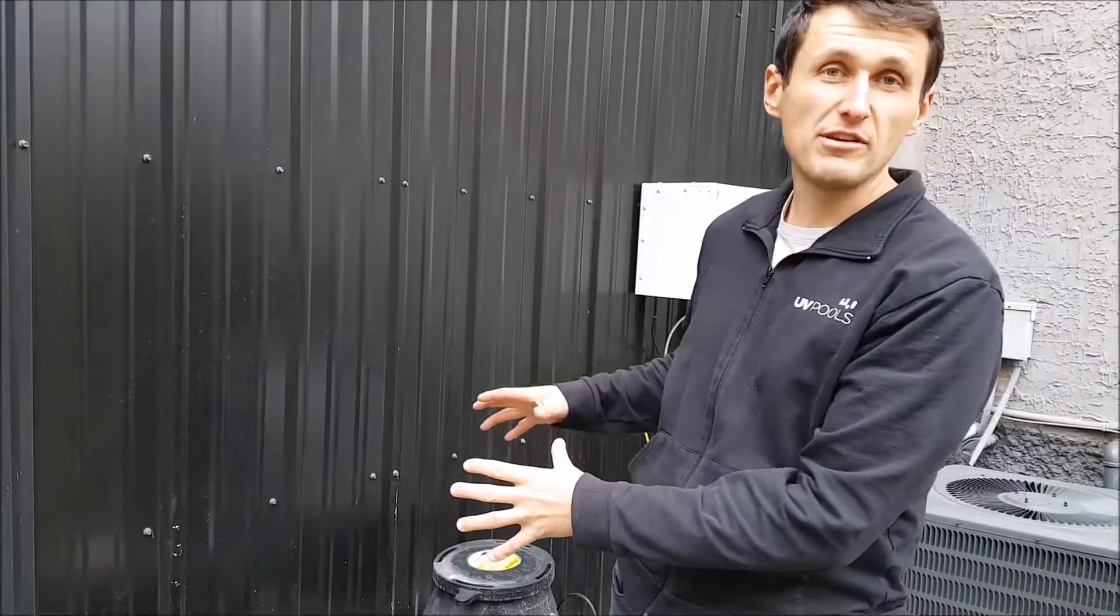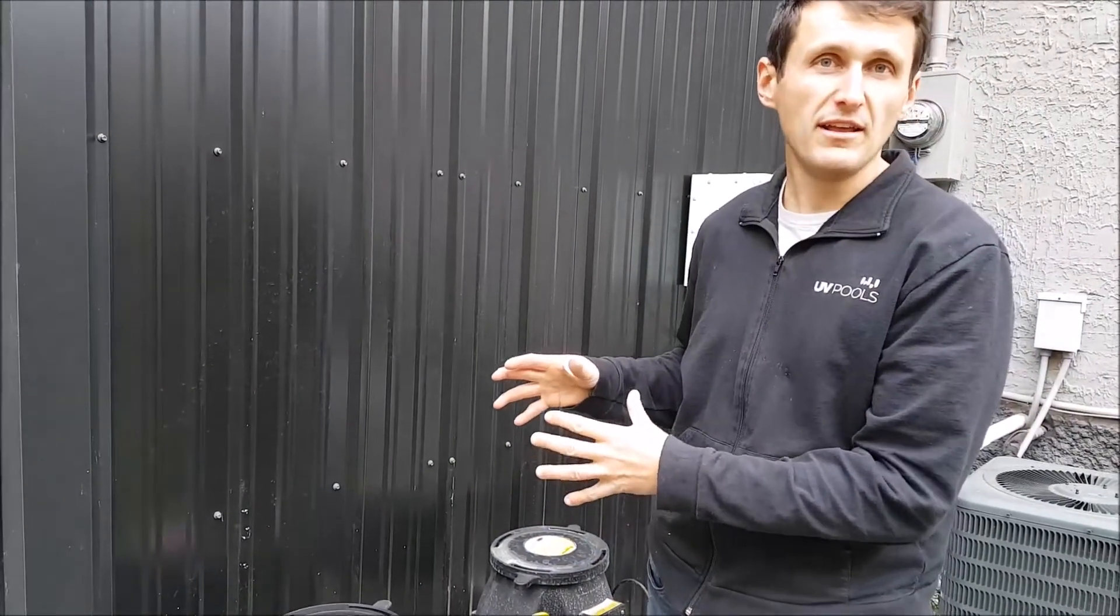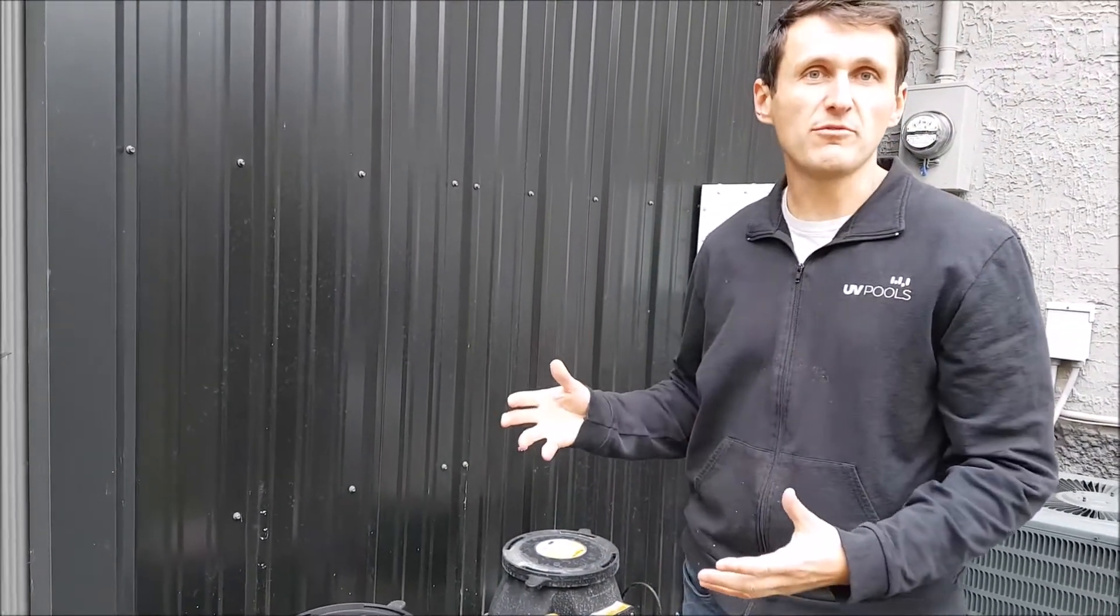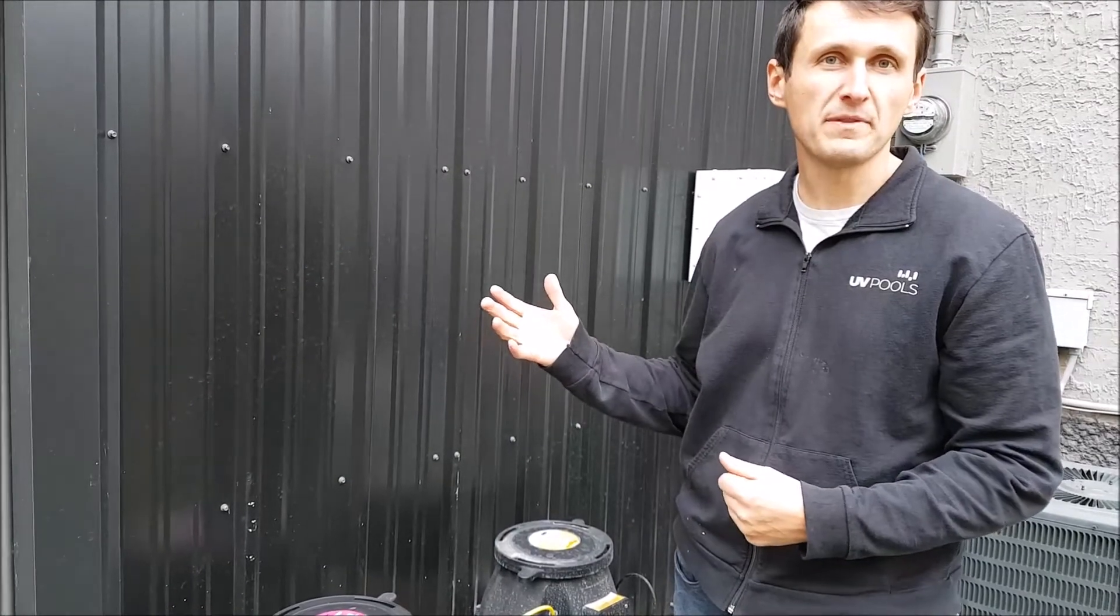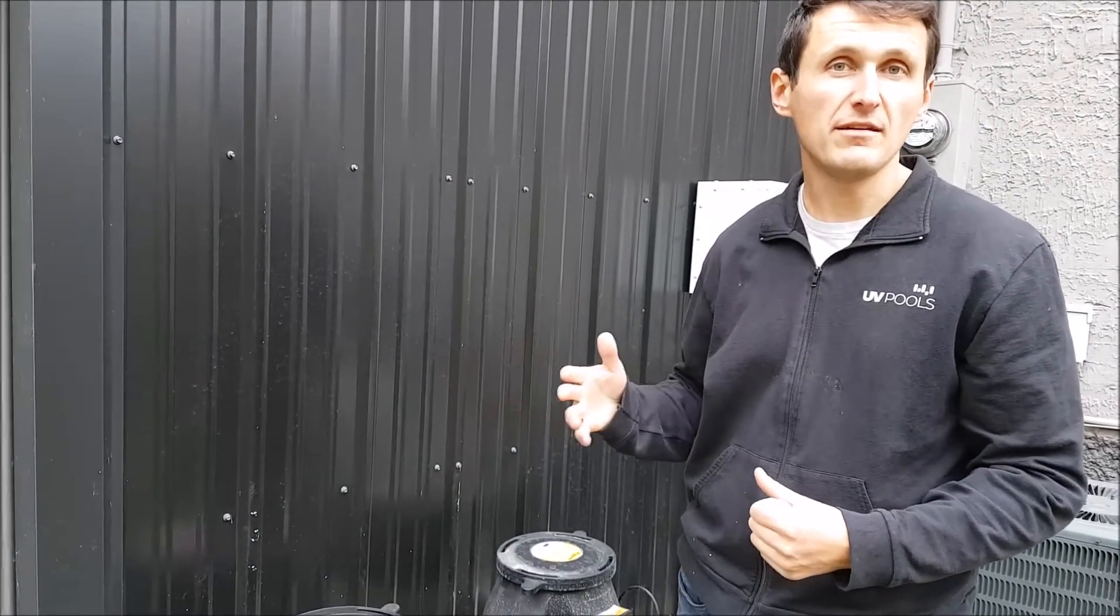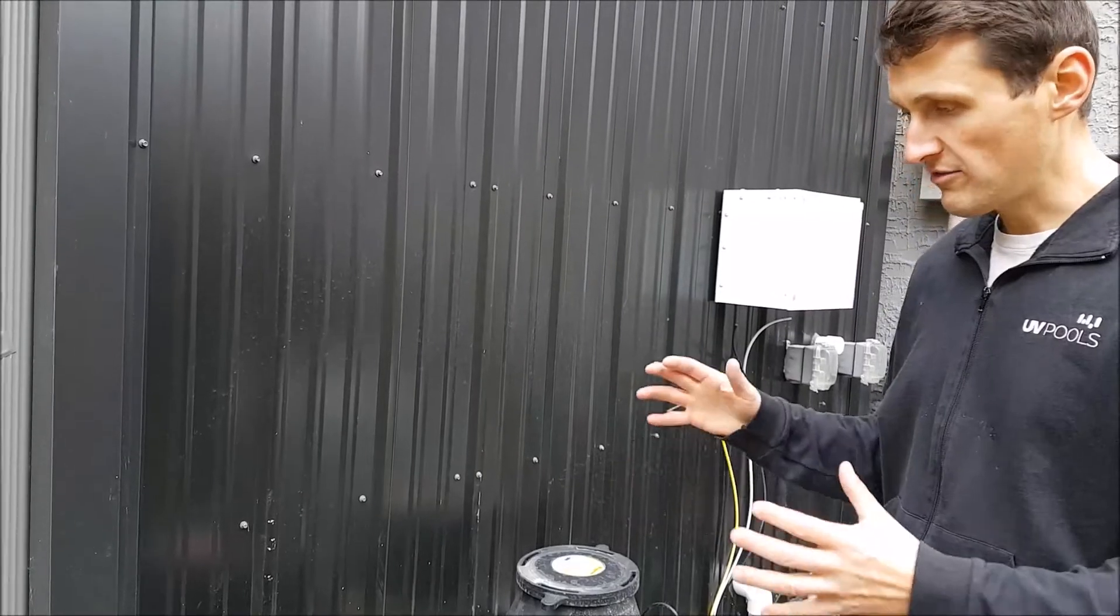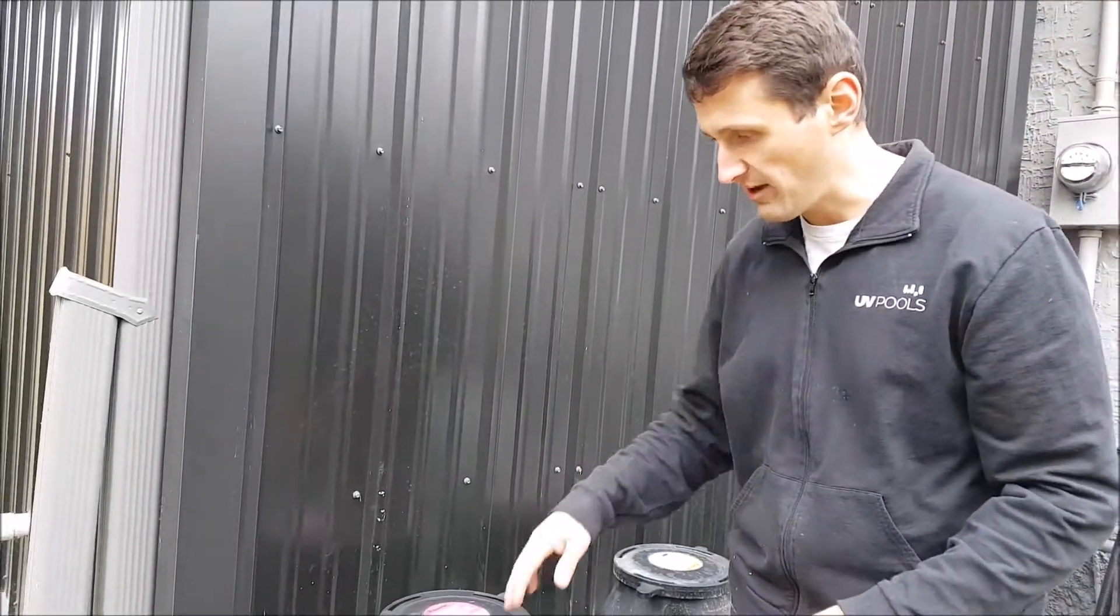We keep the acid and the chlorine outside because they can be corrosive and if you have any leaks, the fumes can rust or oxidize any metal parts or electronics, anything like that. It's always a good idea to keep them outside.